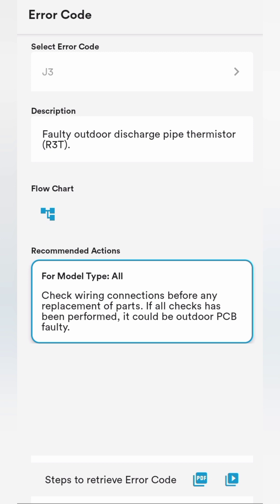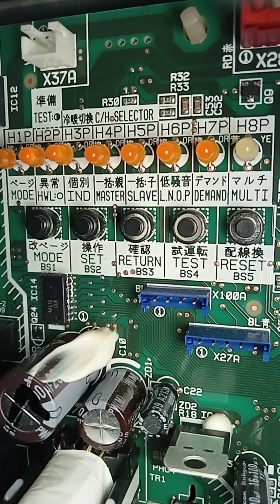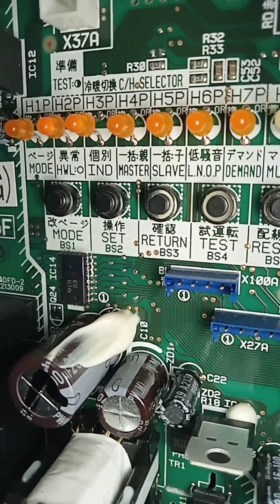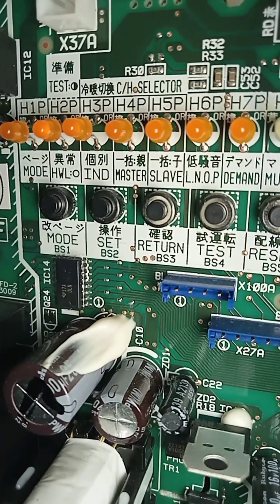This one is the Daikin VRV3 and the error code coming is J3. So we check with the Daikin error code list — it shows pipe thermistors faulty outdoor. So we go and check the main PCB board to see if there is any lighting on the error code indication light.